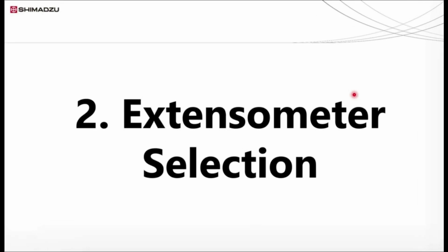Extensometer is another area where many customers make mistakes in selecting a proper one which suits their requirement. For those who don't know what an extensometer is, it is an additional accessory used with the universal testing machine to measure the elongation of the sample with precision. Of course, we can measure the elongation or strain from the crosshead movement also, but sometimes crosshead accuracy is not enough to measure the strain or elongation with precision.